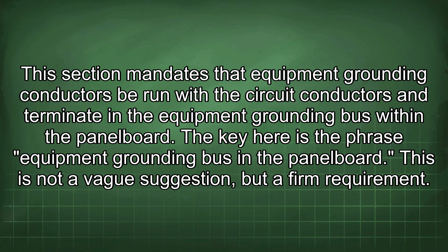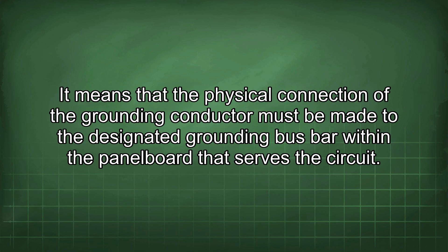The key here is the phrase equipment grounding bus in the panel board. This is not a vague suggestion, but a firm requirement. It means that the physical connection of the grounding conductor must be made to the designated grounding bus bar within the panel board that serves the circuit.